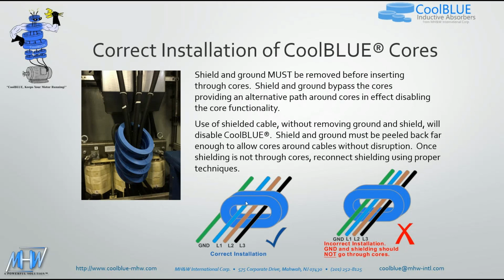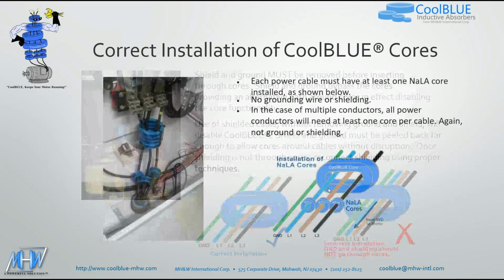And that's not just the ground wire. It's basically any conductive wire. You could put a metal hanger through there, and that would also disable the cores. So through the ID should be only your L1, L2, and L3 leads. With shielded cable, you have to peel back the shielding so that none of the shielding around your cables goes through there. It's just the main copper of L1, L2, and L3. Very, very important. I'll repeat it 50 million times because it's so important.